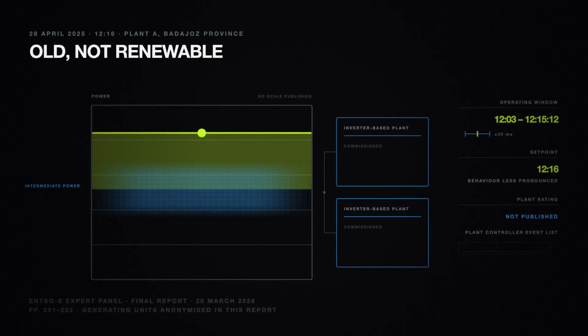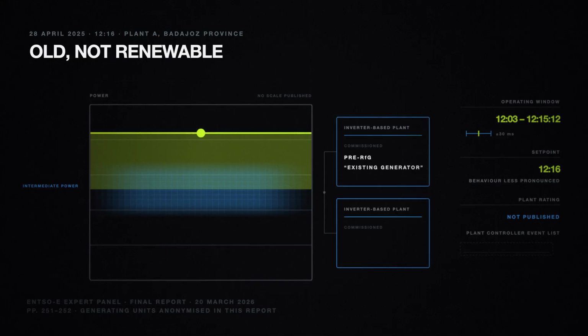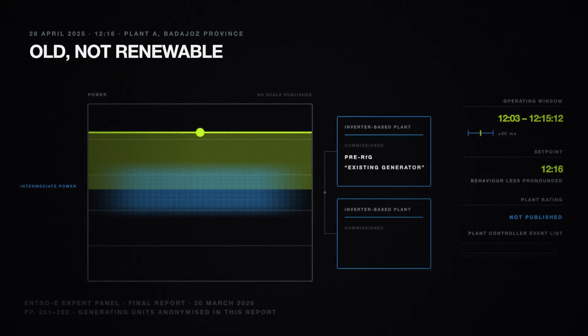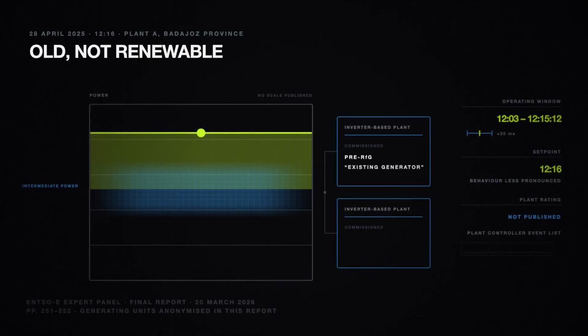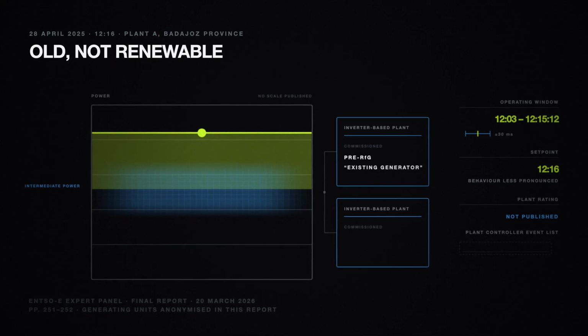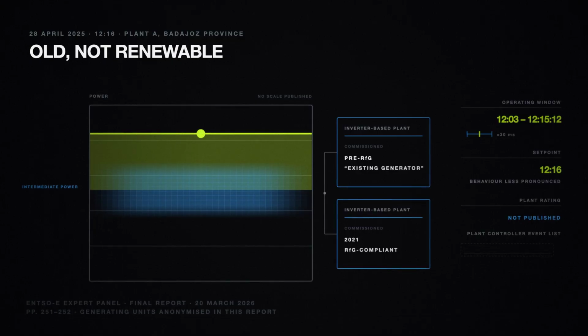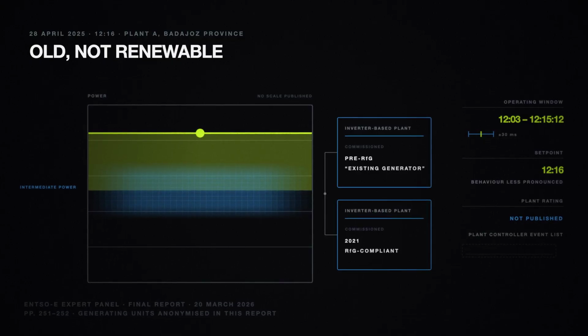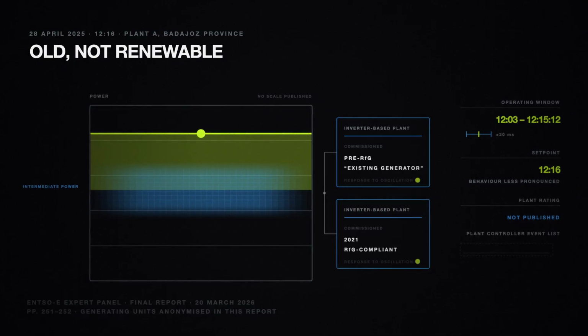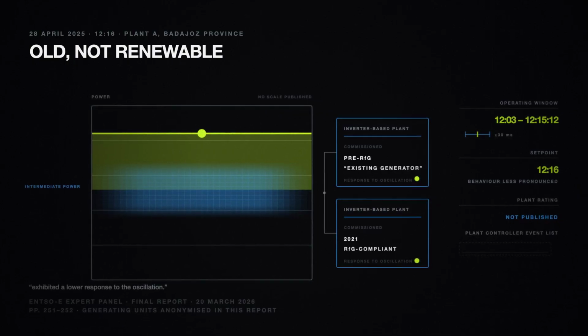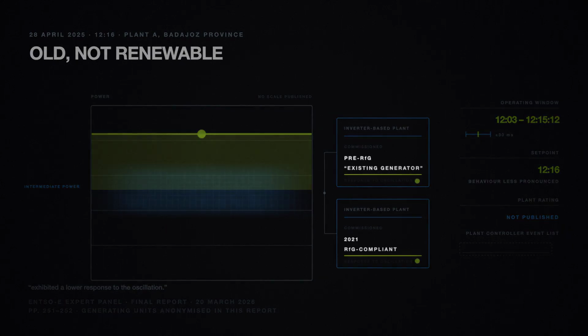The plant was a pre-RfG installation, an existing generator, in the report's phrase, predating the European requirements that apply to new ones. There was a second inverter-based plant on the same node. Same conditions, commissioned in 2021 and compliant with those requirements. It exhibited a lower response to the oscillation. 2 plants, 1 node, 1 difference the report actually names, not what they generate, when they were built.